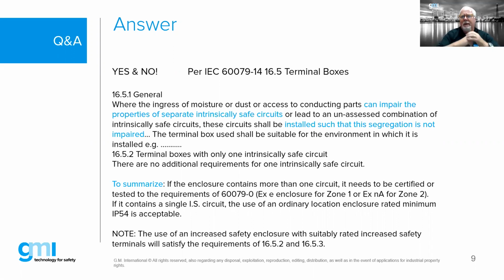So, what is the requirement? The installation design standard is 60079-14, and in 16.5, it talks about terminal boxes. Basically, what it's saying is that if we have a single circuit IS junction box, meaning that we've only got a single circuit, that enclosure does not require an Ex certification, but it must maintain IP54 and it must be marked that it contains an IS circuit. The moment that we add additional circuits into that enclosure, either IS or non-IS, that box in effect would have to be certified. So generally speaking, what people do for more than one circuit is use an Ex e type enclosure with increased safety terminals.